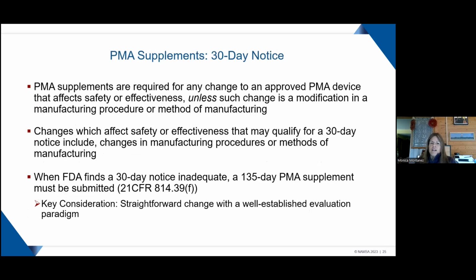So let's talk about 30-day notices. But before we go into that, I want to emphasize that PMA supplements are required for any change to an approved PMA device that affects safety and effectiveness, unless, in this case, such change is a modification in a manufacturing procedure or method of manufacturing. So this particular type of change may qualify for a 30-day notice. When FDA finds a 30-day notice inadequate, they kick it up to a 135-day PMA supplement. So you really want to ensure that you have a straightforward change as well as a well-established evaluation paradigm.